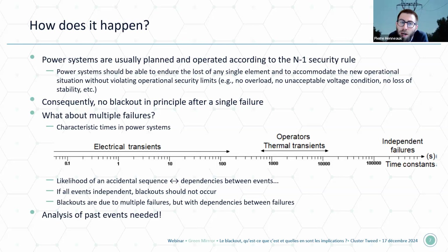Why? It's because power systems are usually planned and operated according to what we call the N-1 security rule. The N-1 security rule states that a power system should be able to endure the loss of any single element among the N initially active elements and to accommodate the new operational situation without violating operational security limits. So basically, you can have the failure of any single element, and afterwards you should not have any overload, any unacceptable voltage condition, any loss of stability, and so on. Because we design, plan, and operate electric power systems in Europe according to this N-1 security rule, we expect that after a single failure, we should not have a blackout. The system should be able to accommodate the new power flows and to supply all the load afterwards.